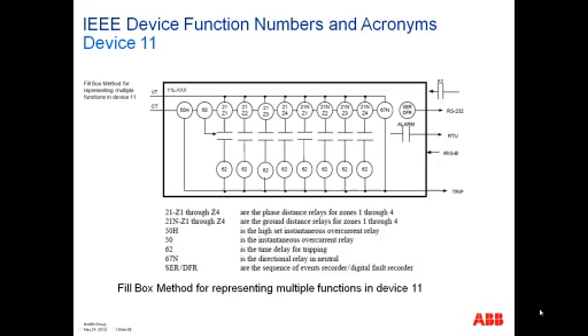This is the method here that I show on the screen that shows you those function numbers, defining what the actual function is. 21 zone 1, 21 zone 2, 21 zone 3, et cetera, and the connections that it may have to other devices. So, like, you have an RS-232, you have an alarm to an RTU, you have an IRIG-B input, and so forth and so on.